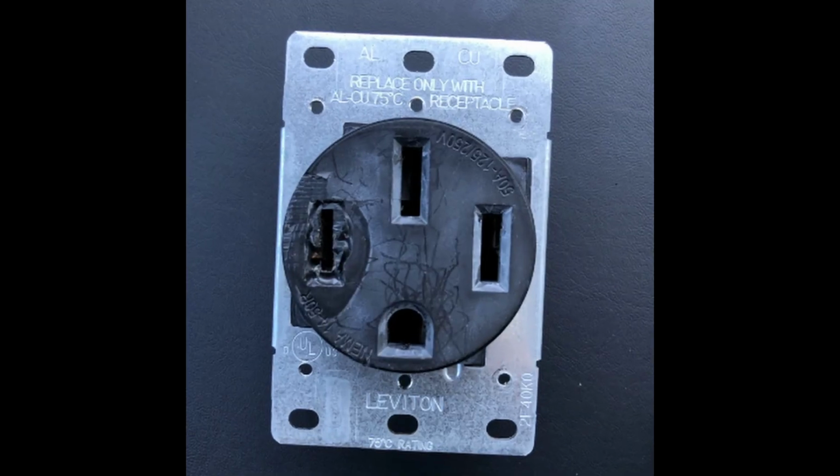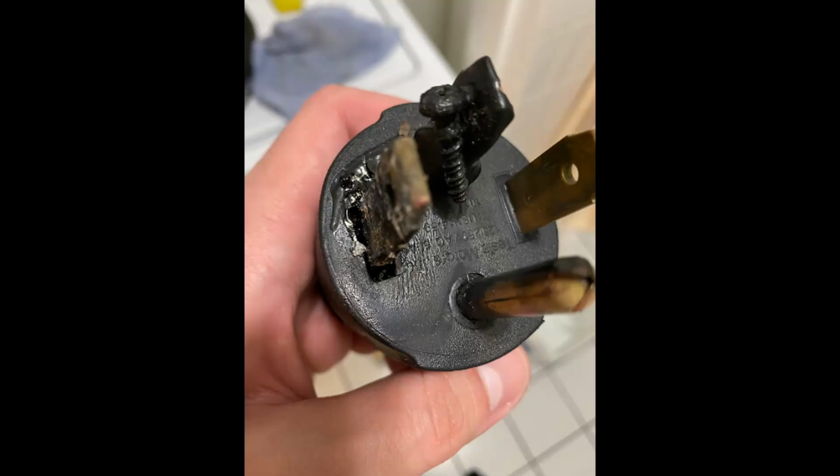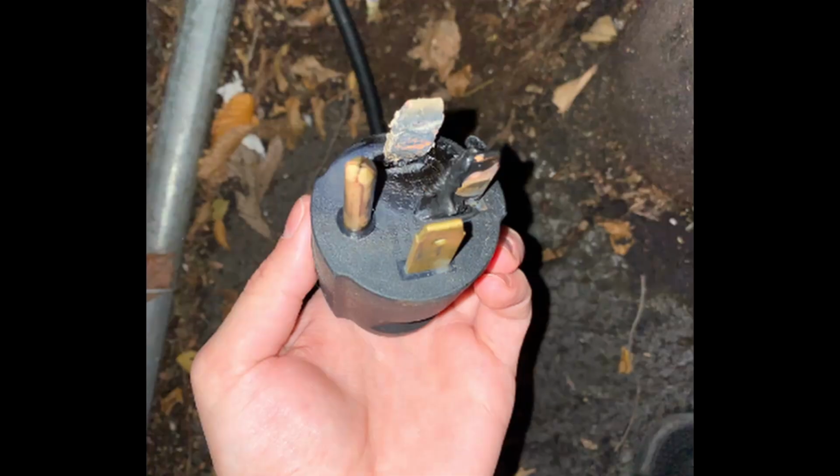Duty. And that's what we're seeing with an electric vehicle. If it requires 30 amps, it's using 30 amps through that entire charging cycle, drawing a lot of power. That puts a lot of wear and tear, a lot of stress, a lot of heat into the outlet, into the plug, and they're finding a lot of these plugs are starting to fail catastrophically, cause structure fires, garage fires during these charging operations.